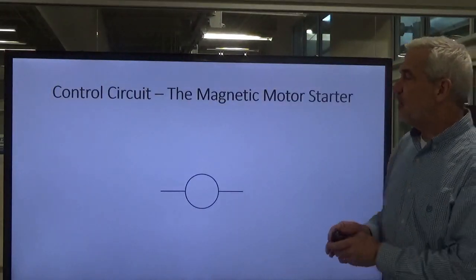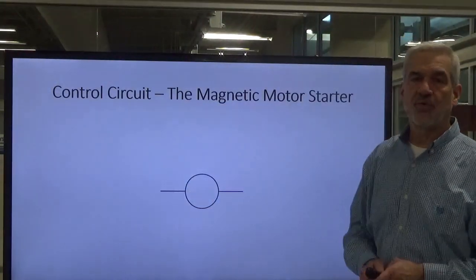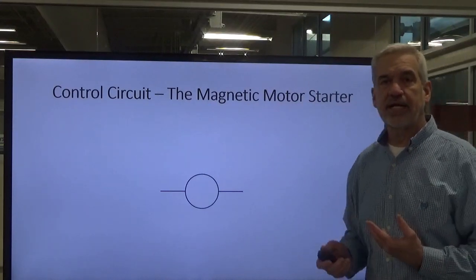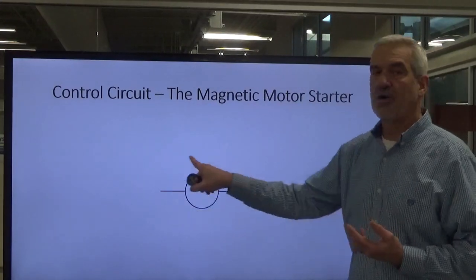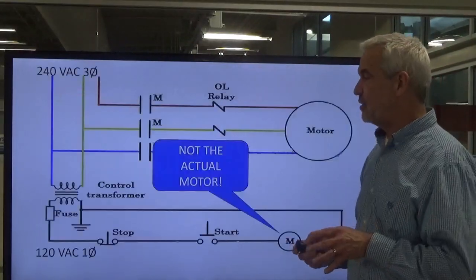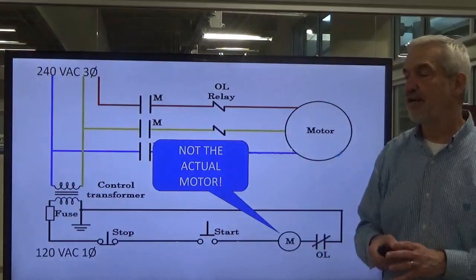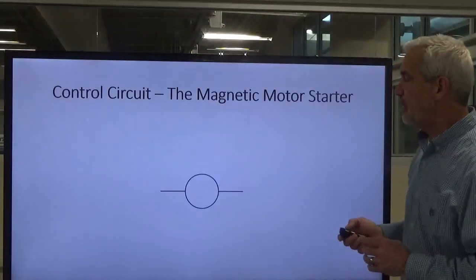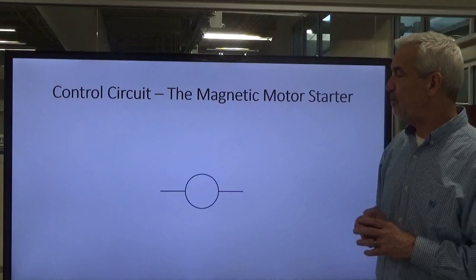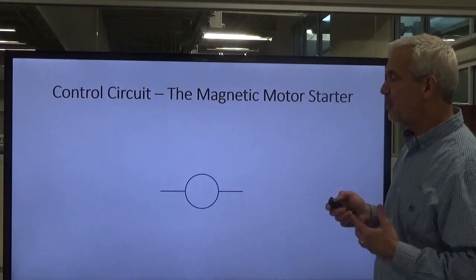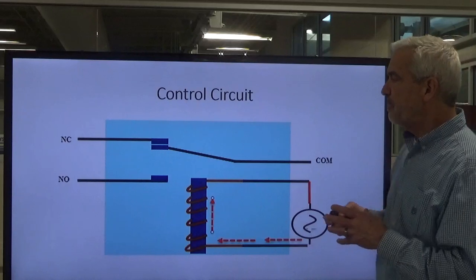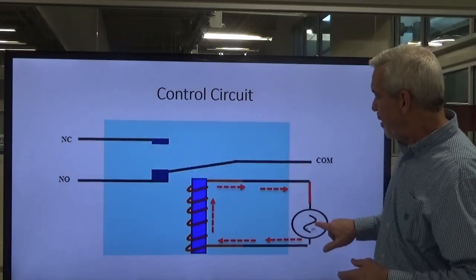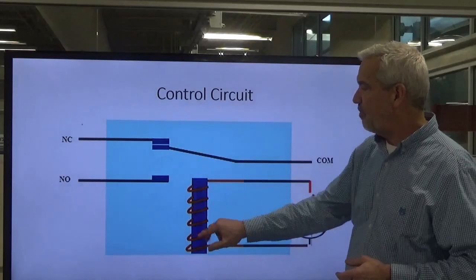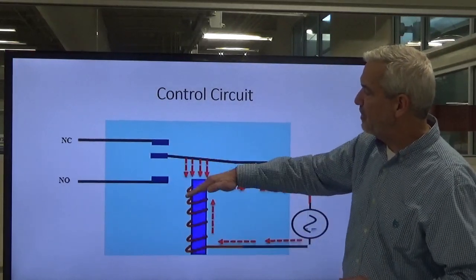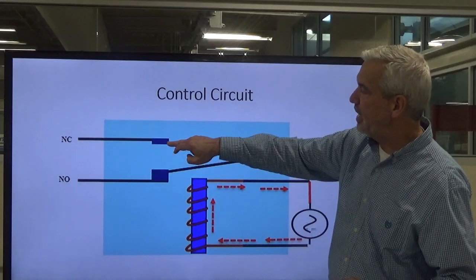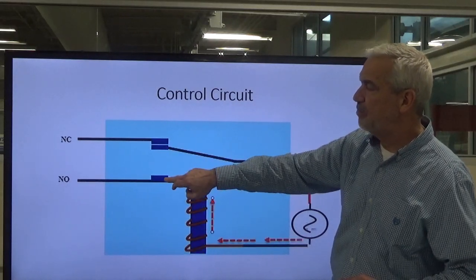Okay? So this is the symbol for a coil, whether it's a relay or a motor starter or a contactor. This is the symbol for a coil. Okay? Now, it's not the same symbol as the coil that you're used to seeing for a transformer, completely different, and they're drawn different for that very purpose. So here's the control symbol for control coil, relay coil, or motor starter coil. Okay, and here's a little graphic, a little file that shows you that when we energize our coil of wire and create that magnetic field, it pulls that armature down and it breaks the normally closed contacts and then closes them on the normally open side.